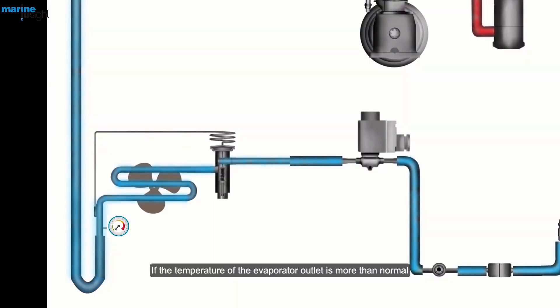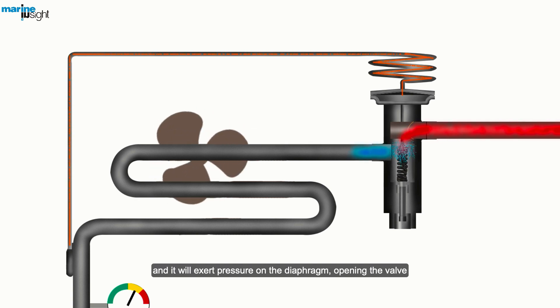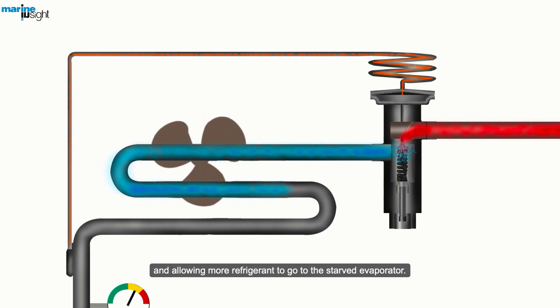If the temperature of the evaporator outlet is more than normal, it indicates that the refrigerant is superheated due to lack of refrigerant. The liquid in the bulb is temperature sensitive and it will exert pressure on the diaphragm, opening the valve and allowing more refrigerant to go to the starved evaporator.